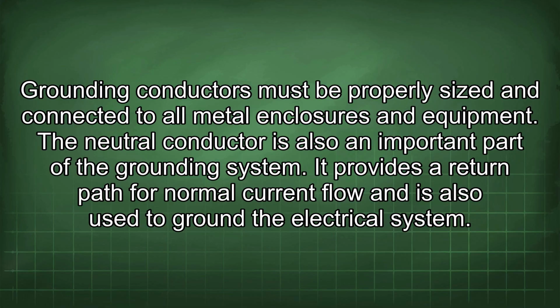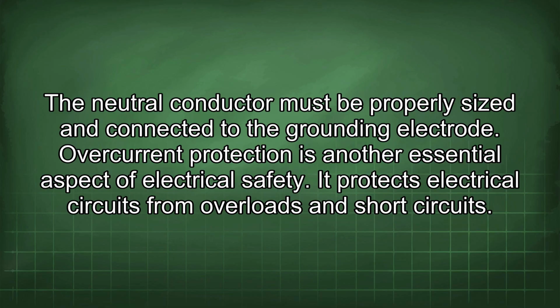The neutral conductor is also an important part of the grounding system. It provides a return path for normal current flow and is also used to ground the electrical system. The neutral conductor must be properly sized and connected to the grounding electrode.